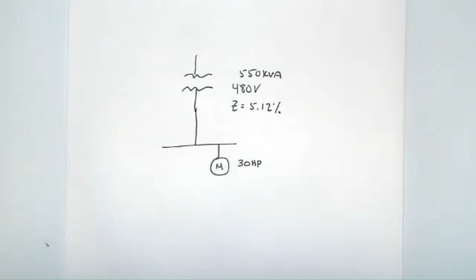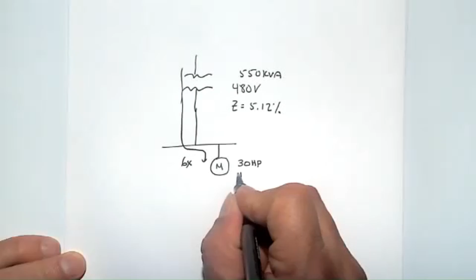So now we're going to do a simple hand calculation based on motor starting to calculate the voltage drop associated with the inrush current of a motor. And as we know, the motor inrush current is typically considered 6 times full load amps. So that current has to flow down through the transformer into the motor. And so when we talk about a motor, we have I full load amps. We can calculate that. But the inrush current is 6 times I full load amps equals inrush.